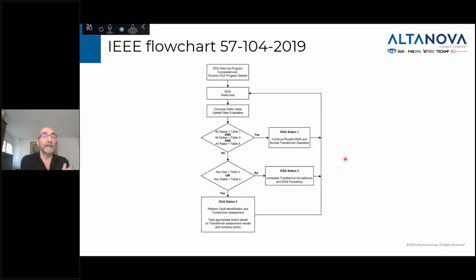The next one that has been developed is the new IEEE flowchart, 57-104-2019. It's a little bit the same principle, but this one takes a lot more into account. The 57-104 has been developed by looking at data from over 100,000 transformers and over 1 million DGAs over the years, and it's a much more thorough analysis of the data of your transformer, but it needs a lot more data. Now you're not just looking at punctual data, but you're going to start looking at the age of your transformer and whether it's a sealed or a free-breather transformer. And you also need historical DGA data to use some of the tables to find what kind of DGA status you have, status 1 or status 2. So as I said, it's a much more complex and thorough analysis than the previous one, the 57-104 of 2008.